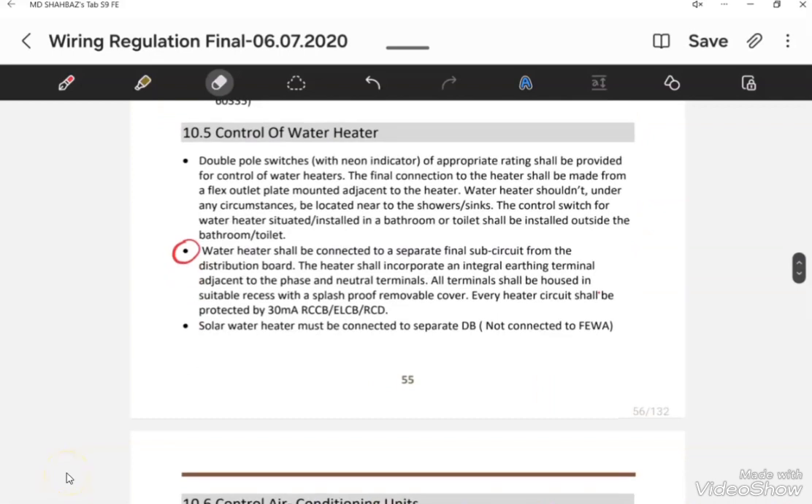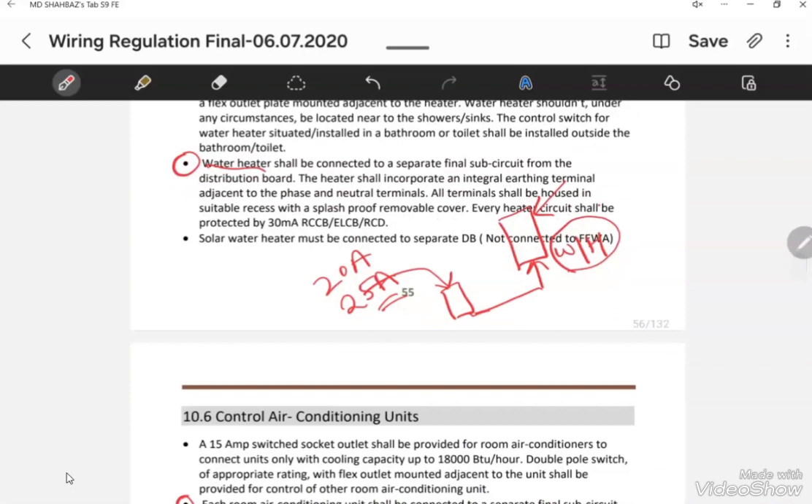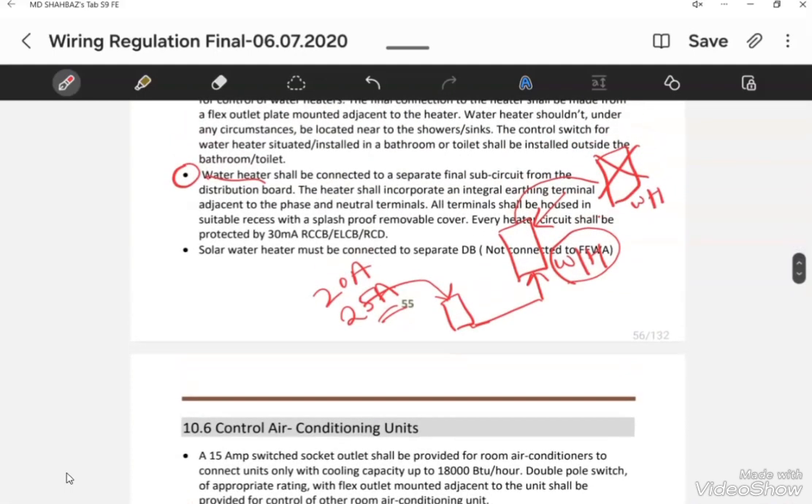For water heaters, they must be fed in a radial fashion, meaning a single breaker will directly feed one water heater. The MCB rating depends on the water heater rating — it can be 20 Ampere for lower loads or 25 Ampere for higher loads. Looping two water heaters on one circuit is not recommended and is strictly prohibited in the FEWA regulation.